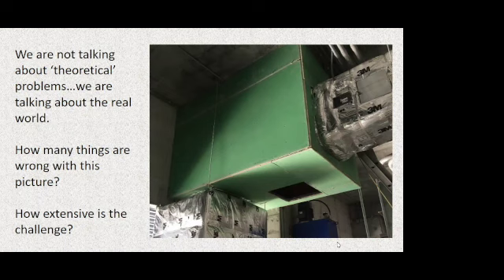But every loose end requires a band. And the collar is the only one that has 2 loose ends underneath of it, which means it needs 2 bands, one on each side of the collar, so that each piece underneath of that collar is properly secured. We only see 1 band. I'm going to show you what happens when you only put 1 band on a collar joint on an insulation class product. The fact that they skip the bands altogether for the plenum box is a complete mystery, because as it gets bigger, you actually need to start pinning 1 or more sides as well as provide bands, so it becomes more stringent, not less stringent, as the duct or the plenum size increases.